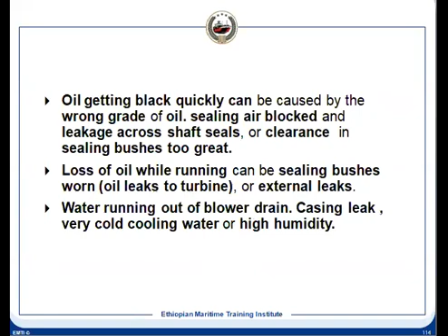In that case, what will happen? If it is because of very cold water, it will get condensed because of the dew point, and the water will come out from the blower drain. If the blower casing is also cooled by water, then water will come from the casing drain. Or with high humidity, moisture gets separated and comes out from the drain. But on the exhaust side, if the exhaust temperature is reduced, then the casing is leaking. Because it is cooled by water, that water goes inside, and you will see the outlet exhaust temperature drop drastically. If you open the drain, you will see water coming out because of the leakage of the turbine side casing.